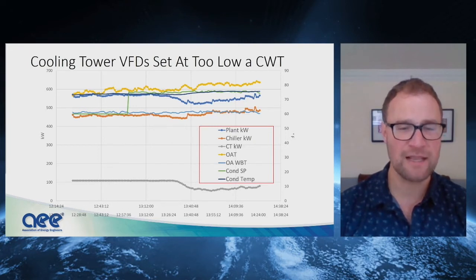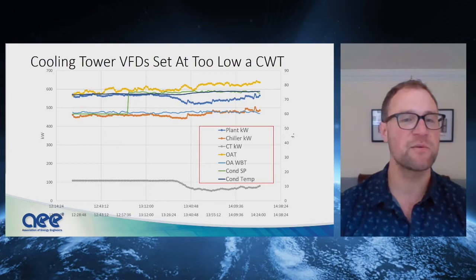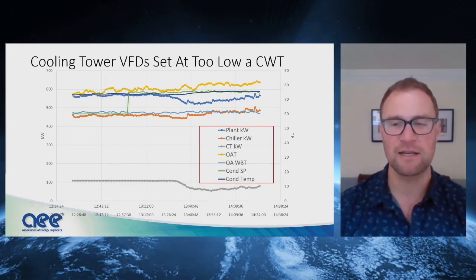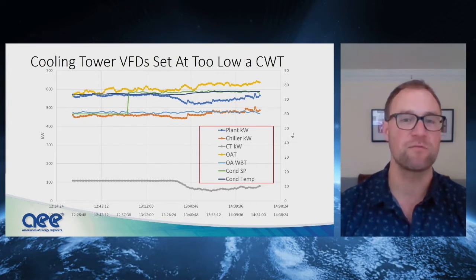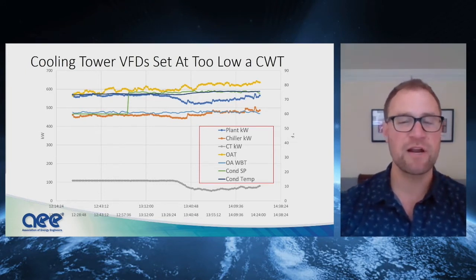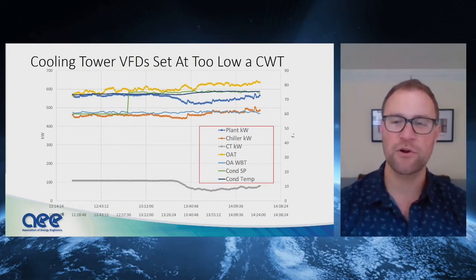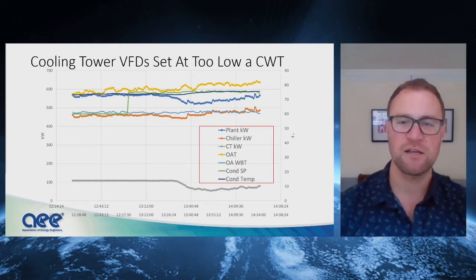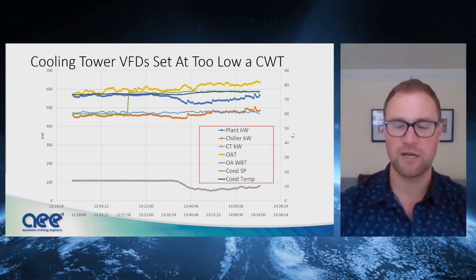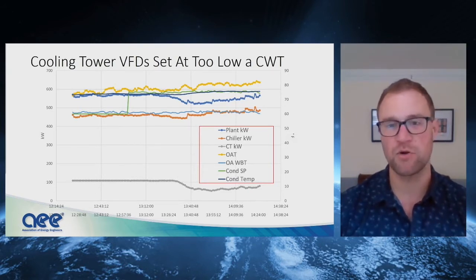And as we see in the gray line on the very bottom, those are the cooling tower fans, and they're pegged at 100% speed. They're trying to keep up, to drive that condenser water temperature as low as the set point was calling for. So we have an opportunity here. We had them program a floating wet bulb approach strategy, which is where you let the condenser water temp follow wet bulb at an offset or an approach.